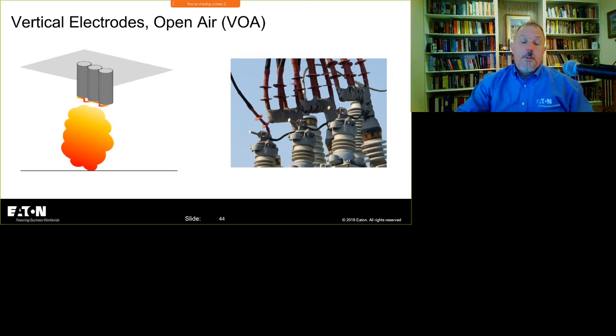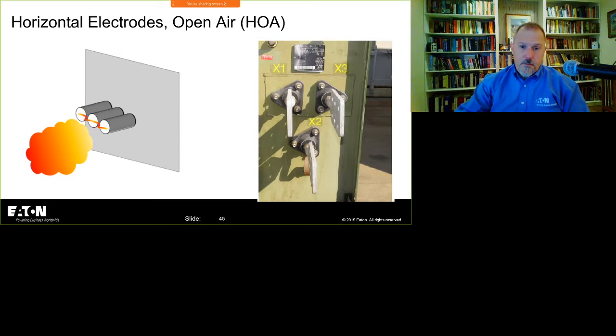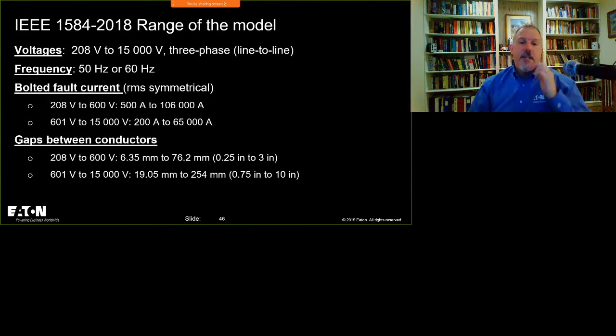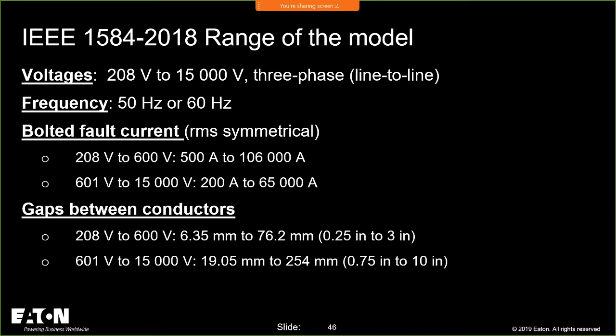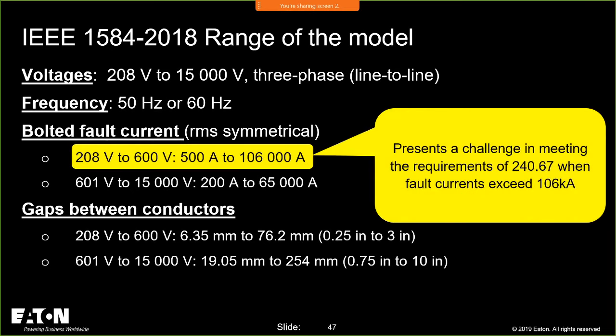Vertical electrodes, that's in your open air. So these are the different types of configurations that you can possibly have when you're calculating incident energy and arcing currents. So these are your range of the model of 1584. You have 208 volts to 15,000 volts, so we're good in voltage. We have frequencies 50 or 60 hertz, and hopefully, I don't know if there's anybody on the phone who works outside of 50 or 60 hertz, but this model only applies in that range. And there's your limiting, there's the first critical factor. It's for 208 to 600 volts, you go from 500 amps to 106,000 amps.